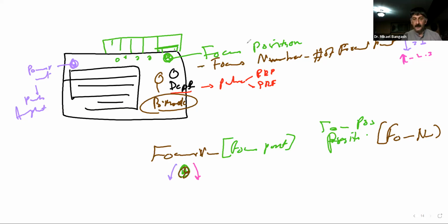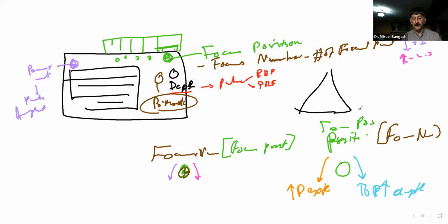Now, when we twist this knob here, if we turn it clockwise, it will move all focal points to greater depths. And vice versa, if we turn it anti-clockwise, it will move the focal points to lesser depths. But please keep in mind, girls, that these focal points can only be shifted up and down within the total depth of your image.